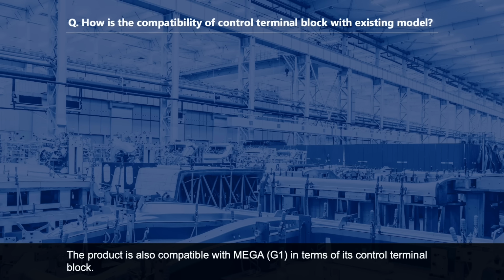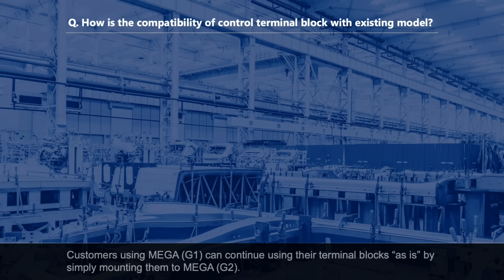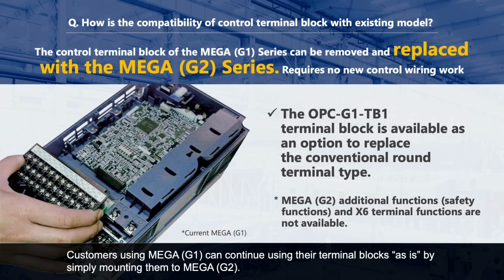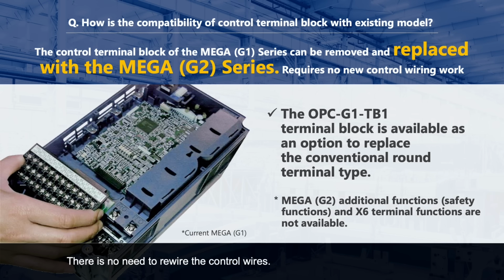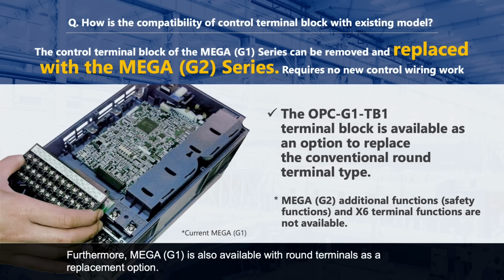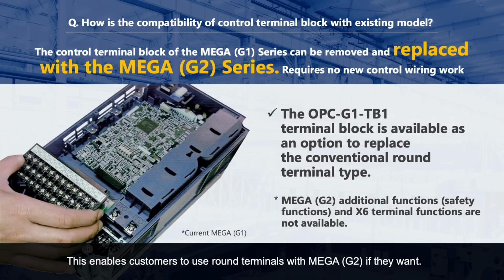The product is also compatible with Mega G1 in terms of its control terminal block. Customers using Mega G1 can continue using their terminal blocks as is by simply mounting them to Mega G2. There is no need to rewire the control wires. Furthermore, Mega G1 is also available with round terminals as a replacement option. This enables customers to use round terminals with Mega G2 if they want. Another feature of this product series is its improved terminal block usability.